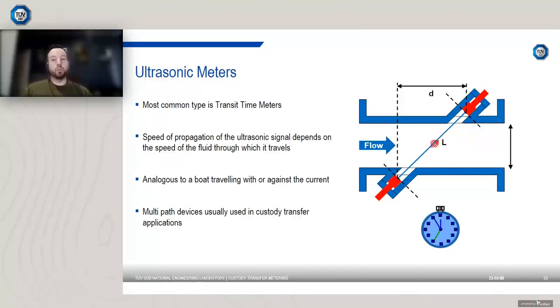I'm going to move on to some of the more modern technologies, although they've been around for a number of years now. And the first one is ultrasonic meters. There's different types of ultrasonic meter. I'm going to focus on transit time meters because they're typically the most common. So how does an ultrasonic meter work?